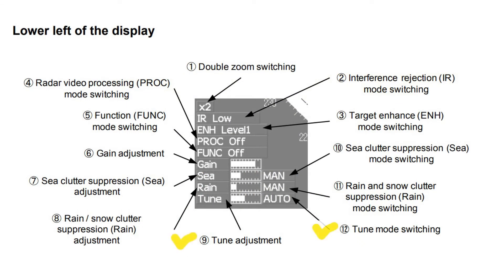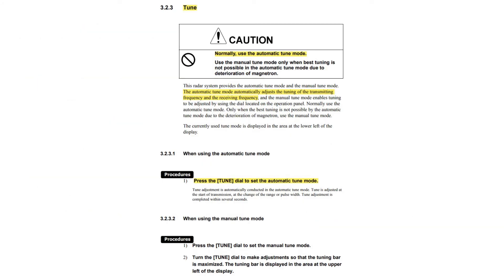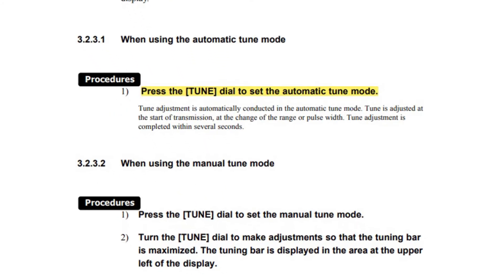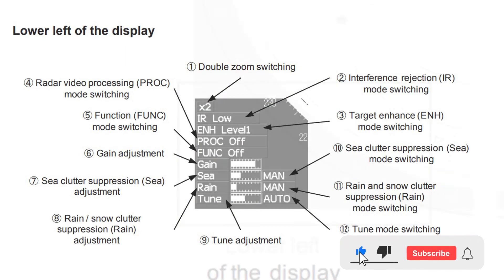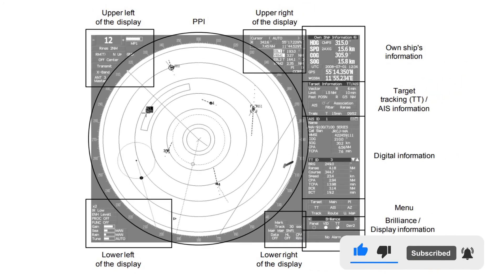Tune adjustment: this radar system provides automatic tune mode and manual tune mode. The automatic tune mode automatically adjusts the tuning of the transmitting and receiving frequencies. The manual tune mode enables tuning to be adjusted using the dial on the operation panel. Normally use the automatic tune mode. Only when the best tuning is not possible by the automatic mode due to deterioration of the magnetron, use the manual tune mode. Thank you very much for watching — subscribe to the channel and see you in the next video.